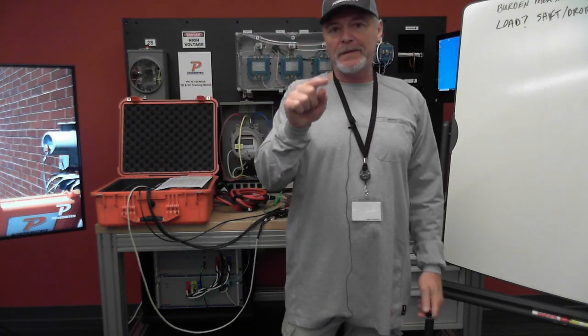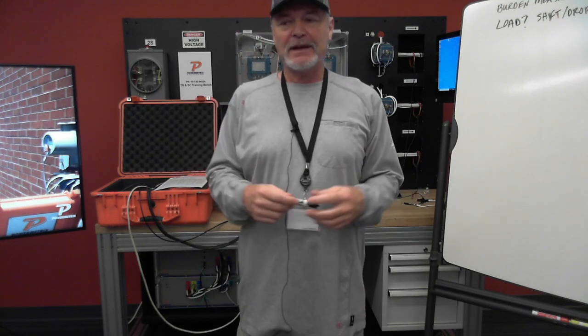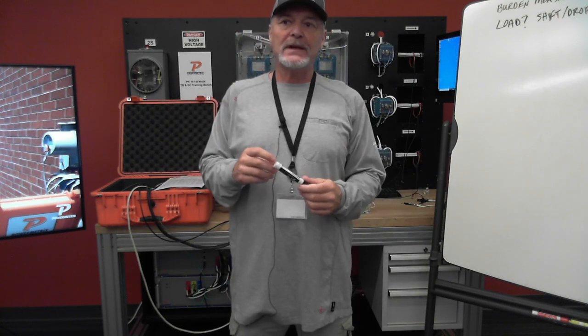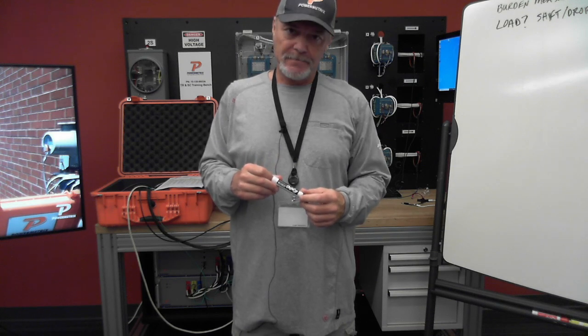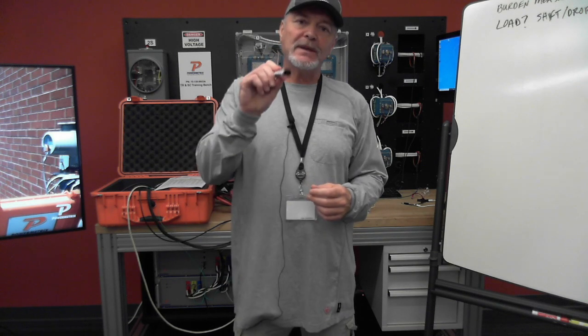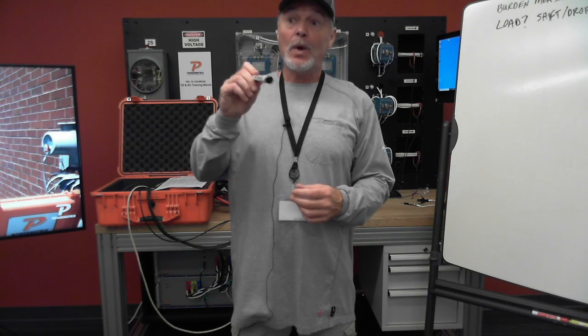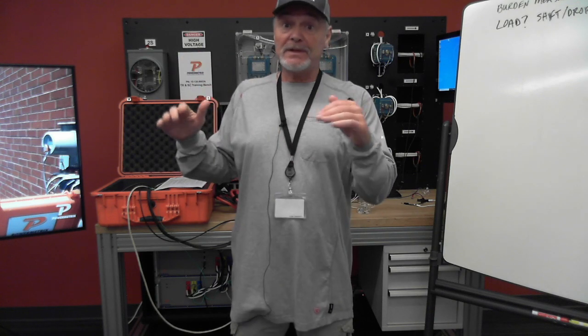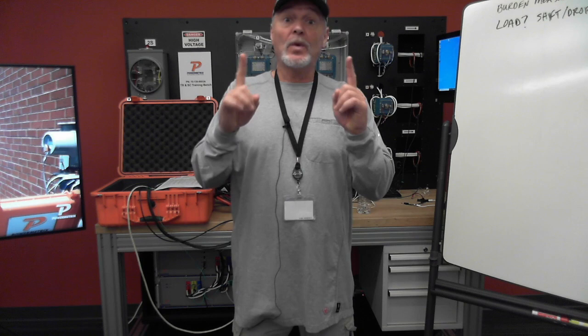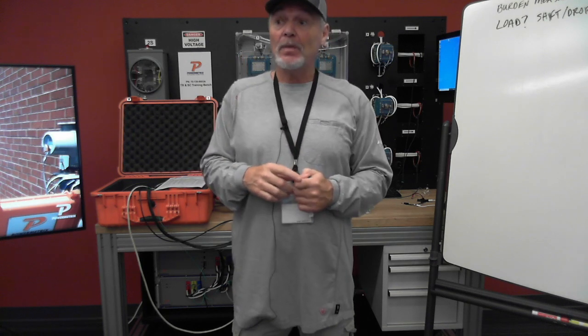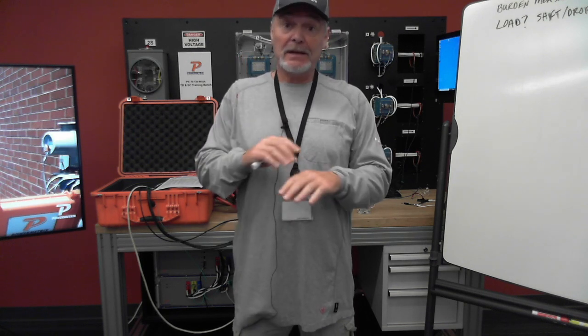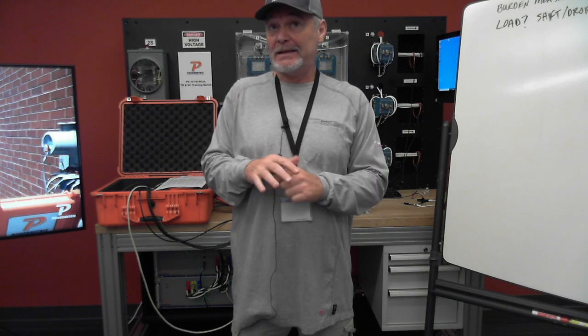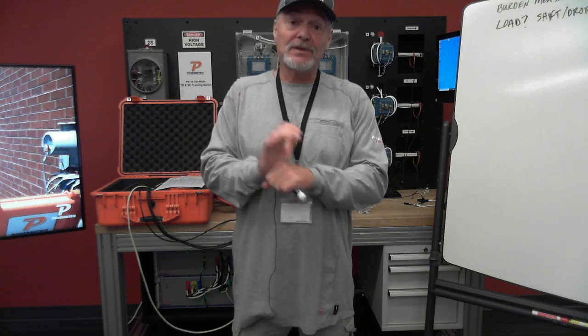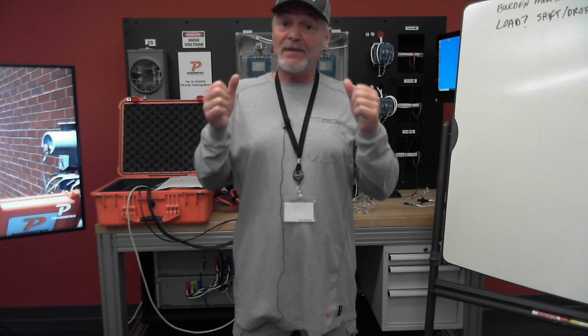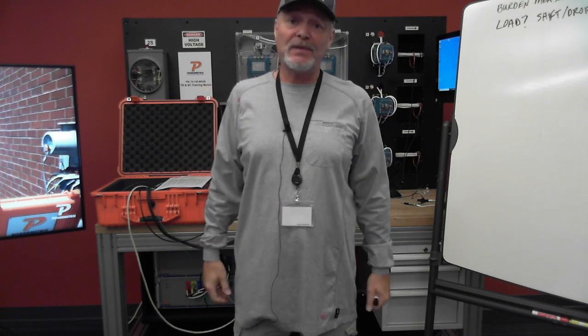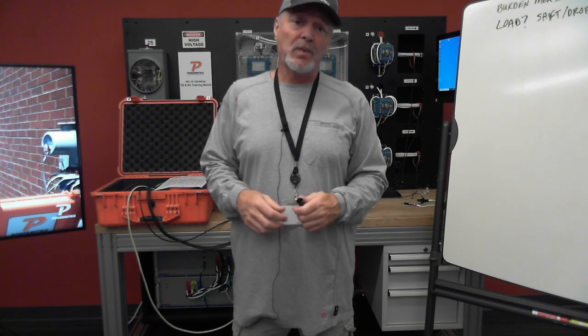Here's where I should have done one more thing. Always in retrospect, right? One thing I should have checked was I should have done a burden measurement test. And if I had done a burden measurement test, then I would have seen what luckily those folks down there knew about, and they asked us to look at one more thing, and I'm going to talk about it here in a second, which is lubricant. And I am not a fan of lubricant, putting lubricant all on those jaws and everything. It eventually hardens up. It's fine going in the first time, but then when you leave it there for years and it hardens up, it's just a source of problems.